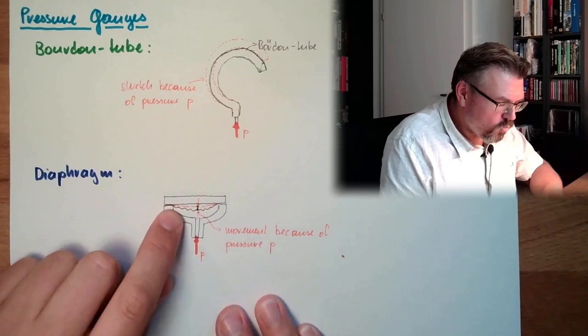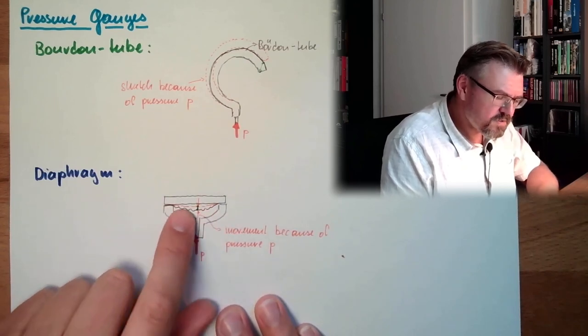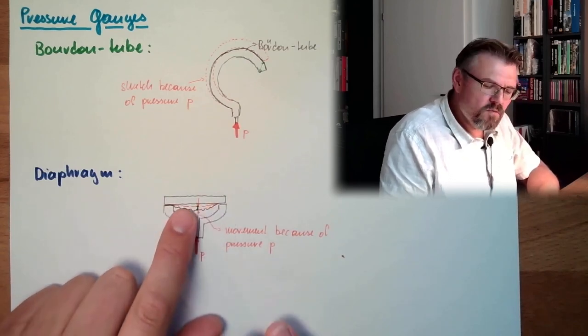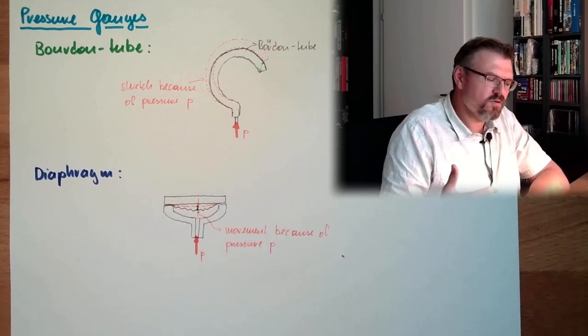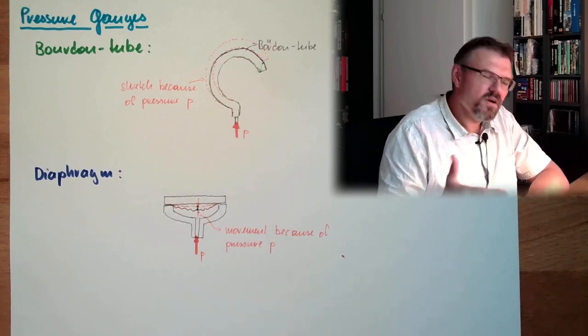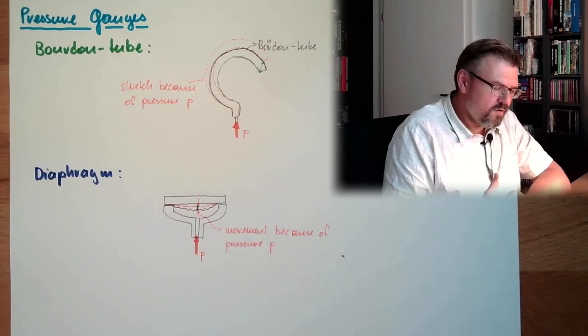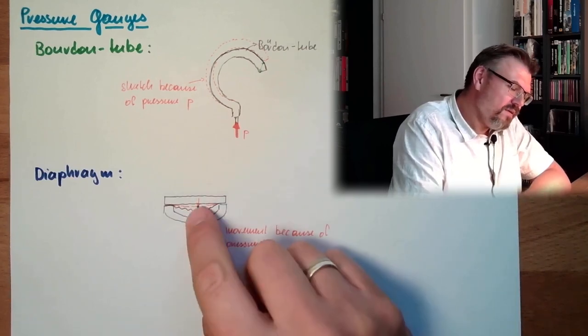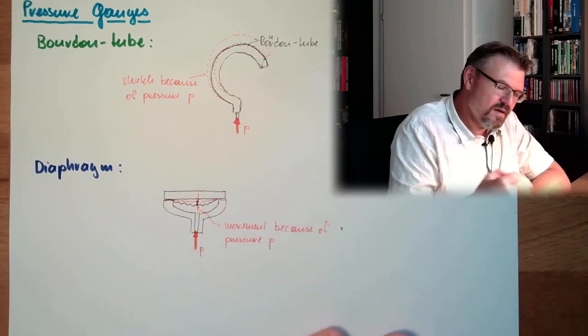Here, I can coat those diaphragms. And I can make the resistance to aggressive materials, to aggressive acid or whatever things, quite high. You see, it's moving a little less than this one, so the sensitivity here is not that high as here.